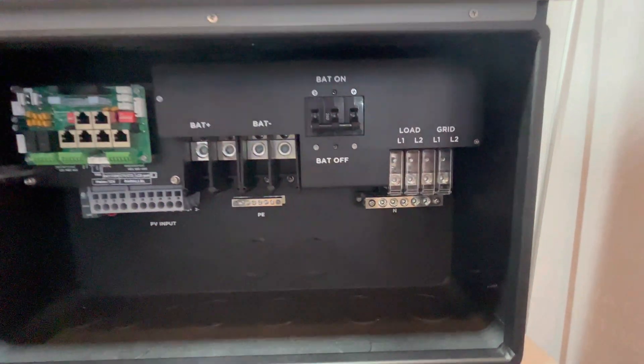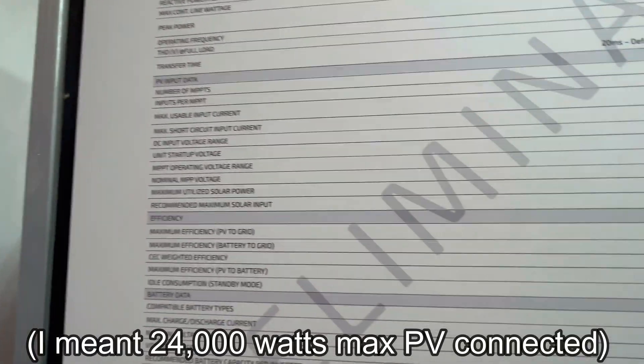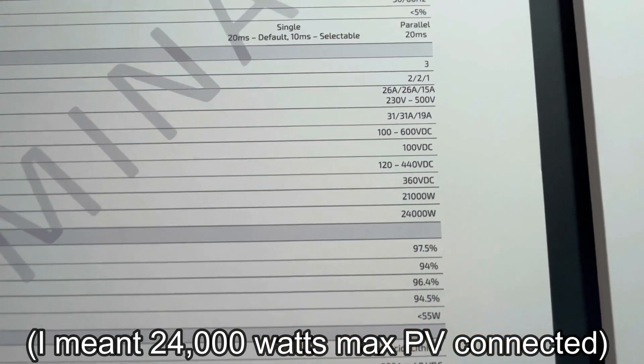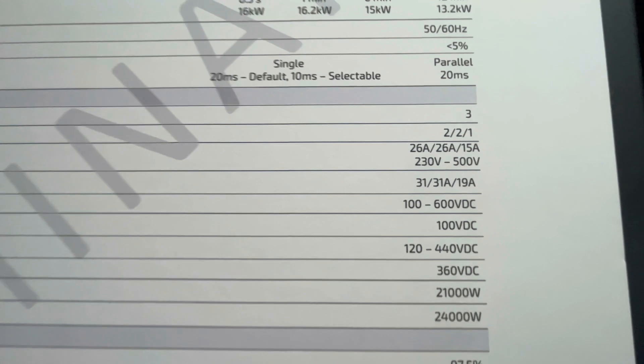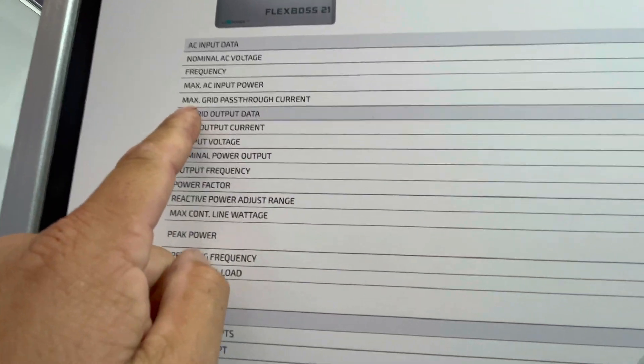It's basically like the 18kpv, a little bit bigger and a little bit stronger, because you can do 24,000 watts maximum of solar power connected to it. Your typical 500 volts DC — 230 volts to 500 volts is the recommended range. But the max grid pass-through on the 18kpv was 200 amps.